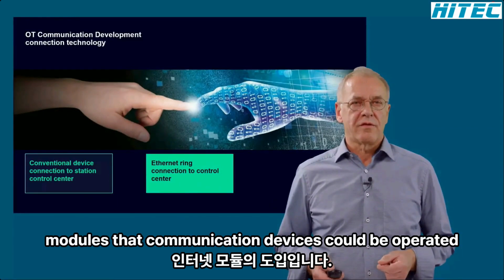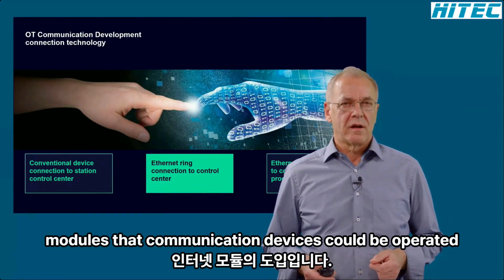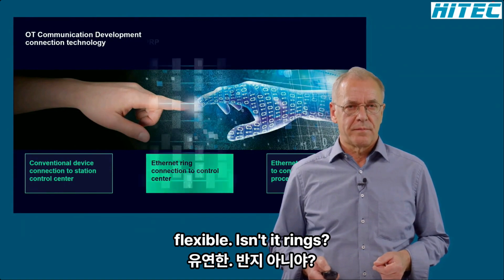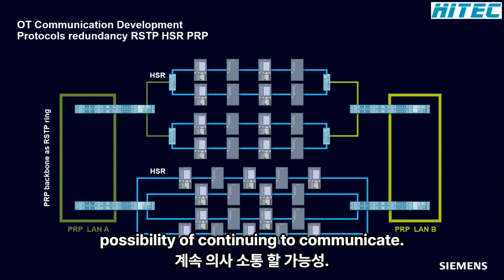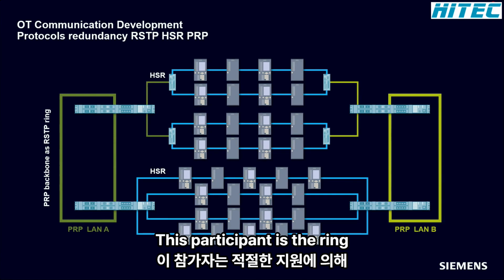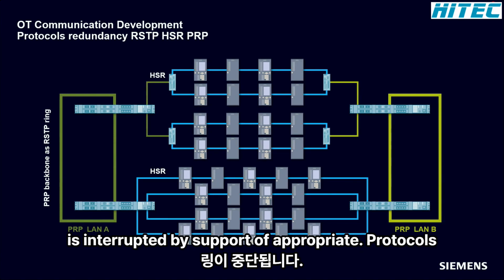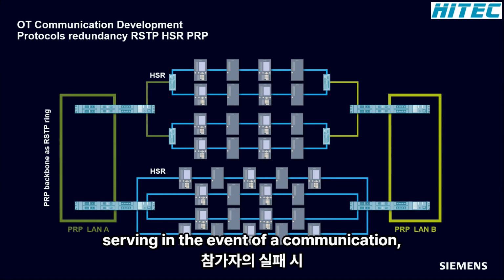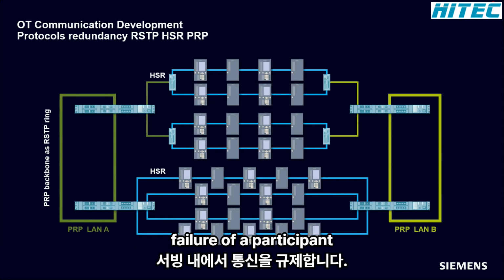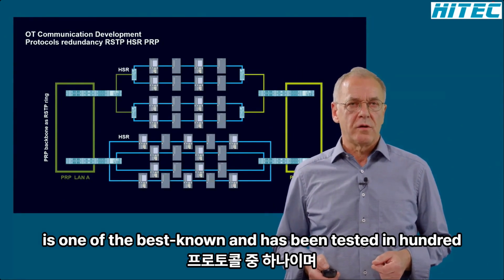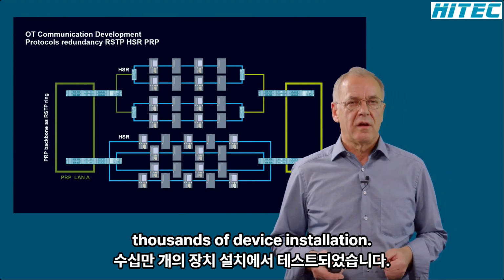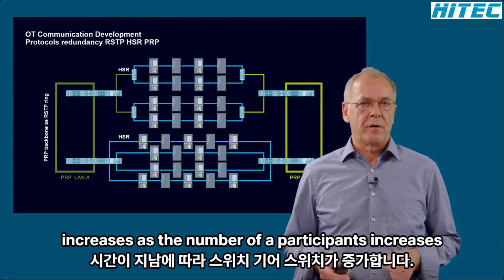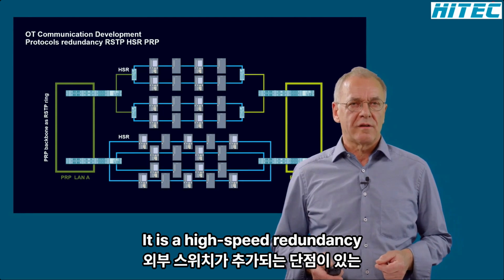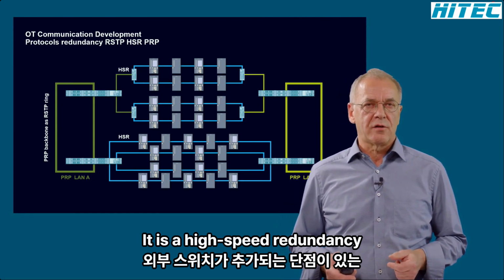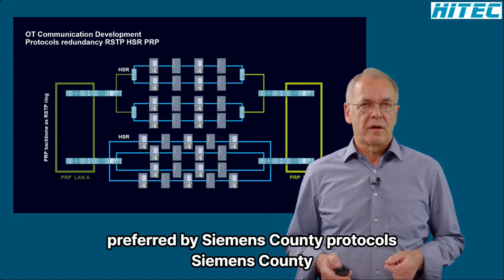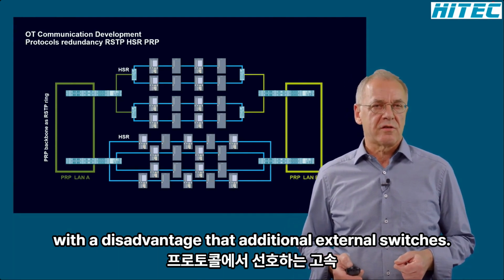With the introduction of the Ethernet modules, the communication devices could be operated in flexible Ethernet rings. These Ethernet rings offer the possibility of continuing to communicate with the participants if the ring is interrupted, by support of appropriate redundancy protocols. The redundancy protocols regulate the communication within the ring in the event of a communication failure of a participant. RSTP, the rapid spanning tree protocol, is one of the best known and has been tested in 100,000 device installations. The switchover time increases as the number of participants increases. Therefore, the following seamless switching protocols were introduced. HSR, high-speed redundancy, preferred by Siemens. PRP, parallel redundancy protocol, with the disadvantage that additional external switches are necessary.